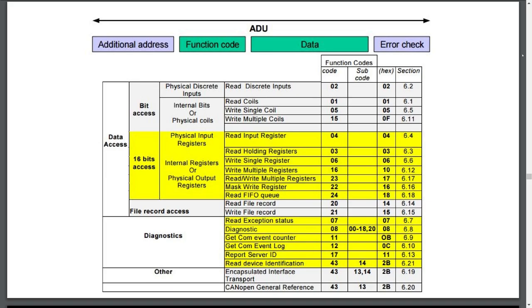Some of the more popular function codes are listed on the bottom-right diagram. This includes function code 1, read coil bit status, function code 2, read input status, function code 5, write single coil status, and we have some other write function codes such as 6, 15, and 16.